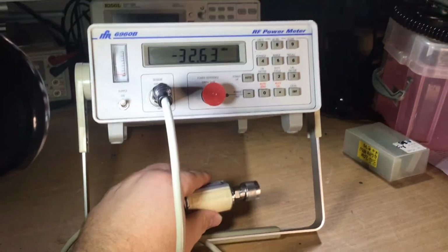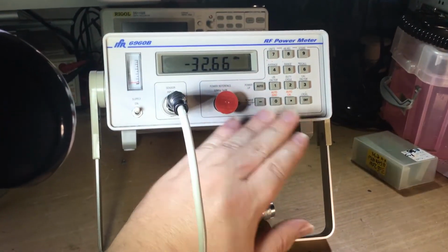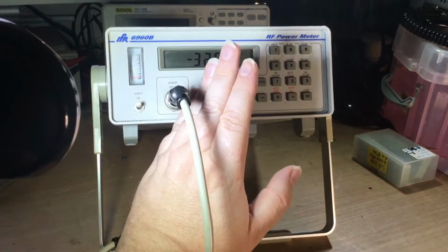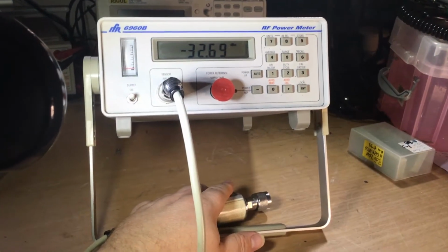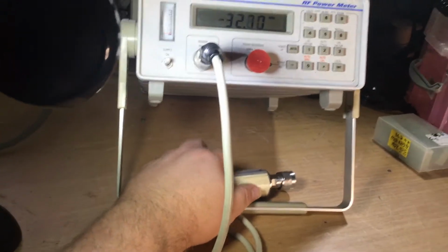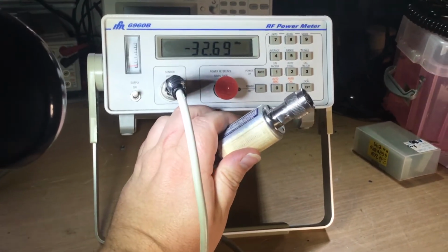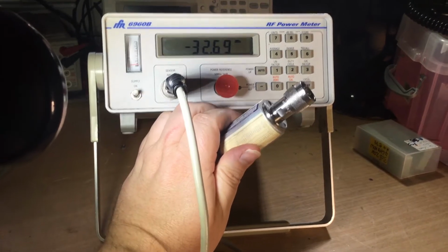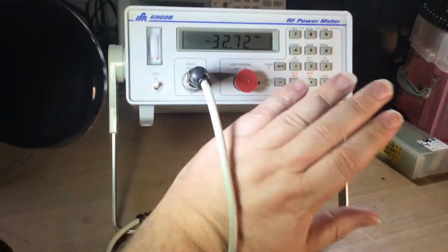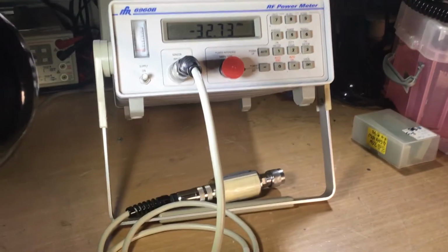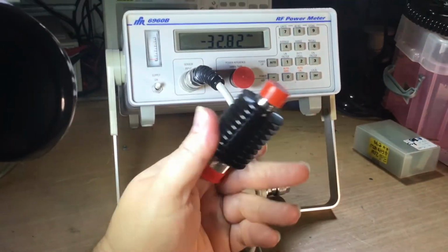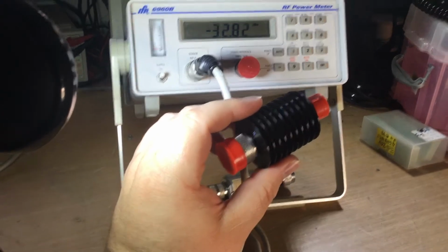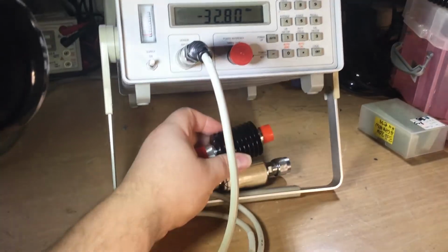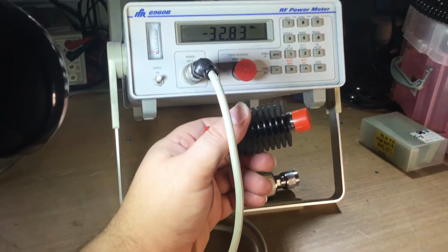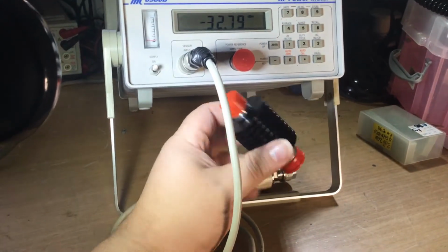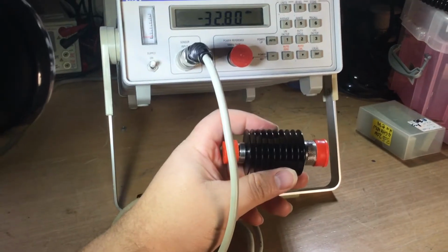Now the meter itself is designed to measure from a very low RF level of just microwatts right the way up to kilowatts if you use the right sensors with it, but most of the Marconi range of sensors only go up to milliwatts or a few watts here or there, not really high power levels. So how you achieve the high power measurement capability on this is you use external attenuators such as this one. Now this goes up to 4 gigahertz, which is adequate for this sensor, because obviously that goes up to 4.2 gigahertz as well. So you would use a level of attenuation to reduce the signal down to a safe level.